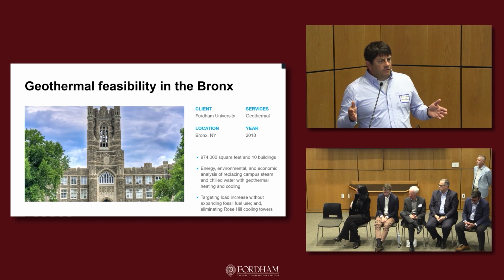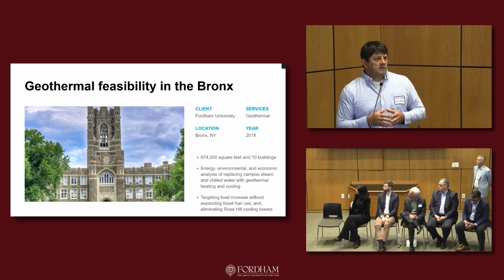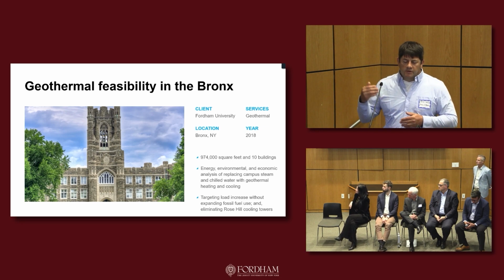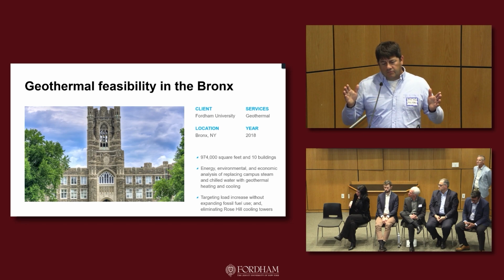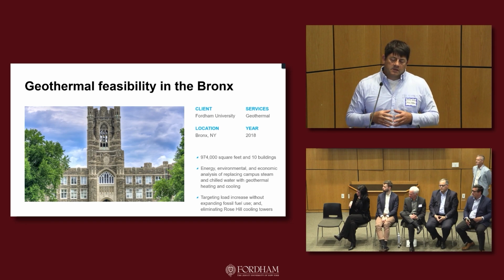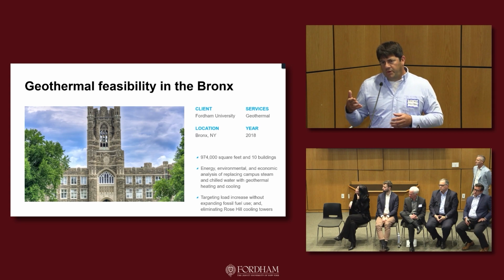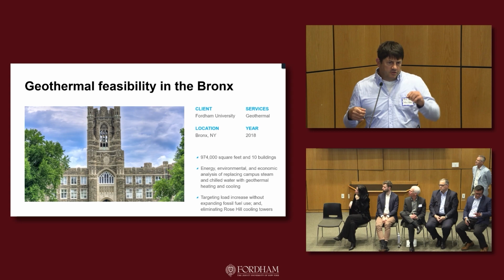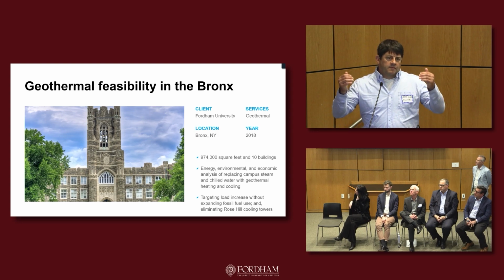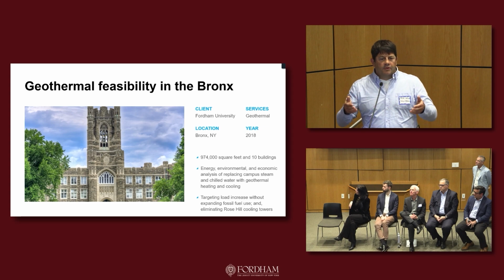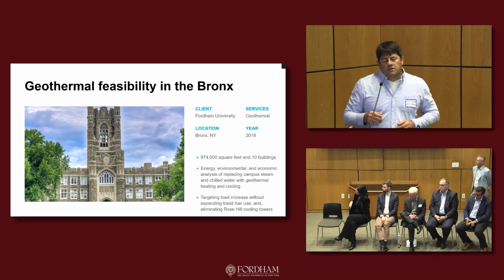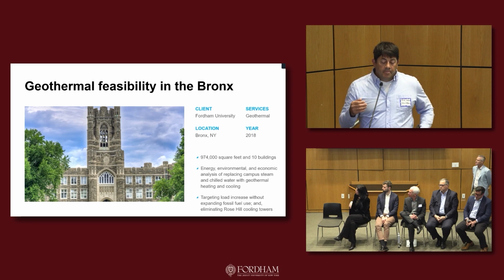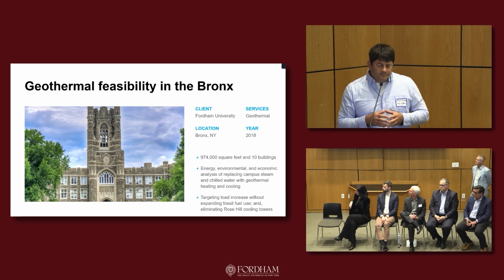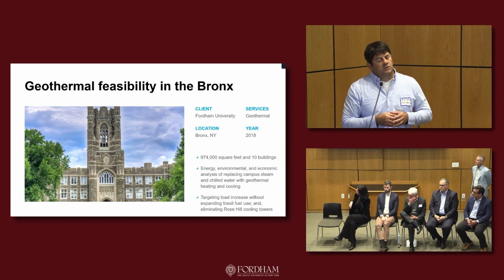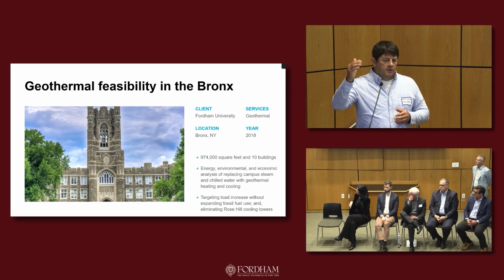Now, when we do campus conversions, folks, 50% of all the first cost is building conversions, because typically they're either a steam building or steam heat, radiators, coils. And some buildings actually have a shell and tube heat exchanger, steam to water temperature, 200, 180, right? For us to convert those buildings down to 130, 120, 110, whatever it may be, it takes a lot of time and money. So we may then put in a high lift heat pump at that building level connected into our district system as our energy source, and we'll lift just that one building to 180 or 190.